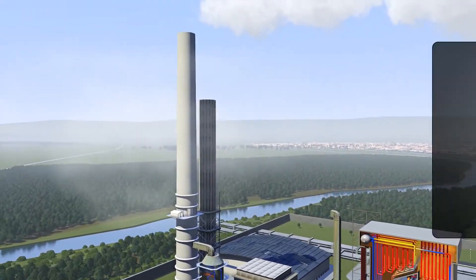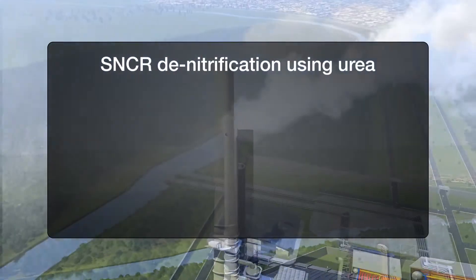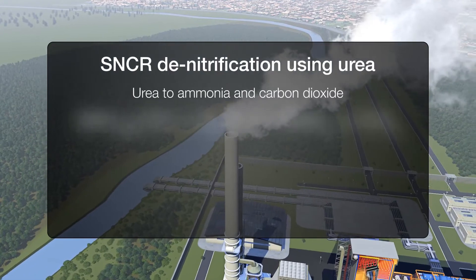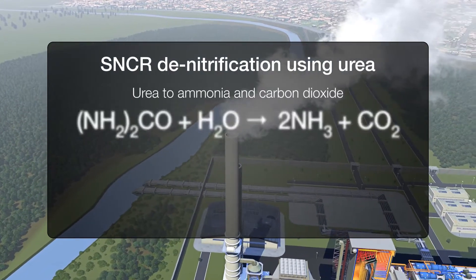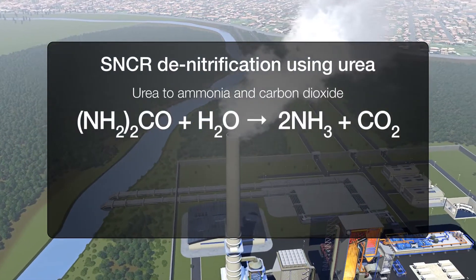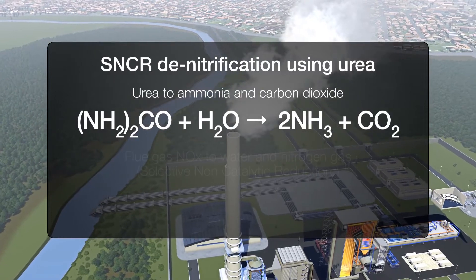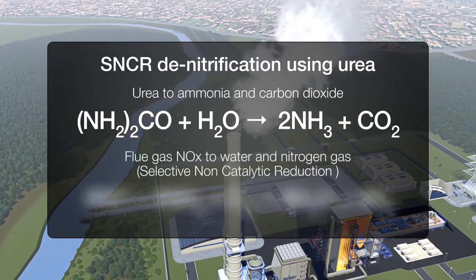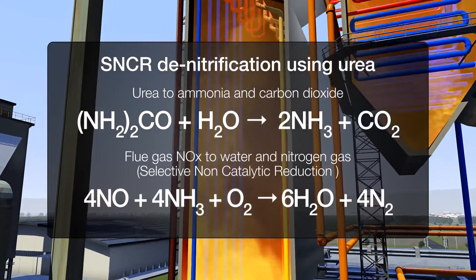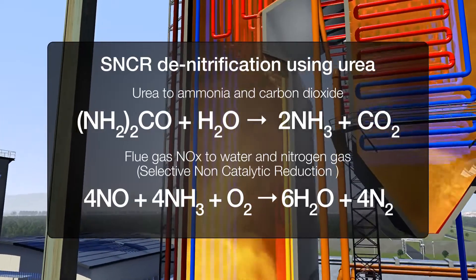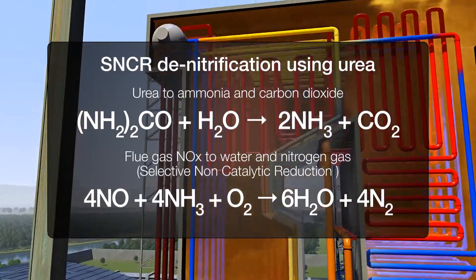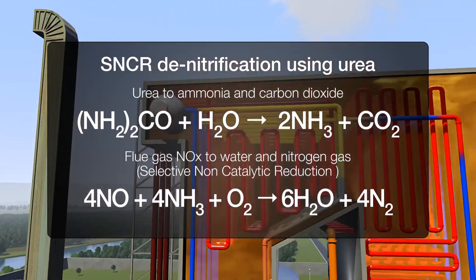Selective non-catalytic reduction, or SNCR, plants are less efficient, removing around 70% of NOx, but use urea which is cheaper and easier to use than ammonia. The urea is added to the furnace to break the NOx down into nitrogen, carbon dioxide, and water.